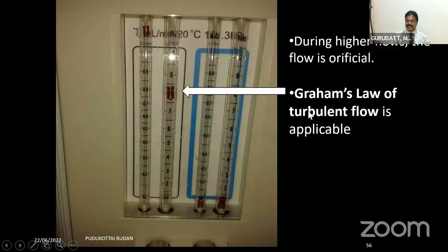When you are setting higher flows, because the flow becomes turbulent or orificial, the flow is inversely proportional to the square root of density. Since the density alters in high altitude areas, suppose these flow meters are calibrated at 760 millimeters of mercury and you take this machine to a high altitude area. Because the density is less, the flow will be much higher than what you think you are giving. That's the reason you have to calibrate these flow meters for that altitude before using.